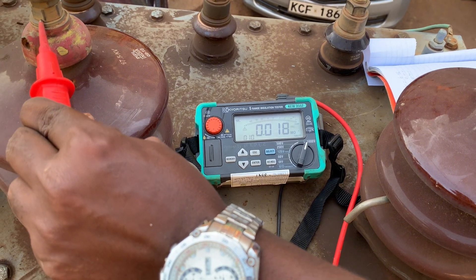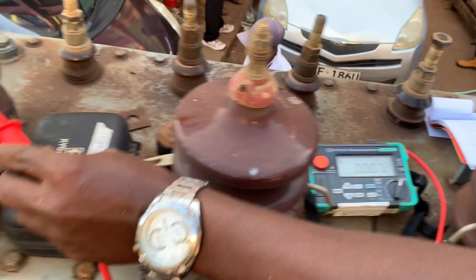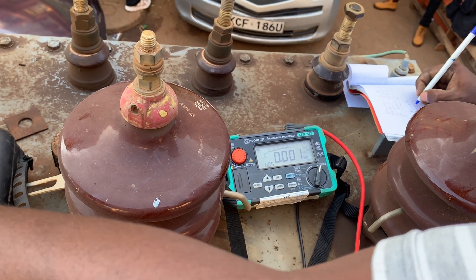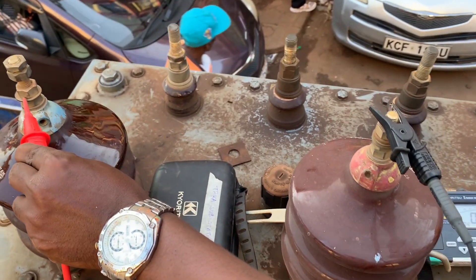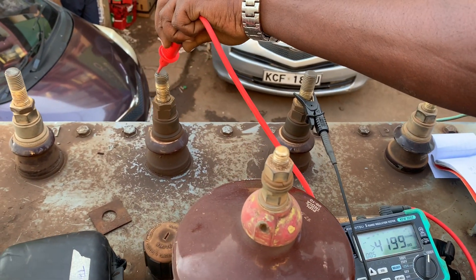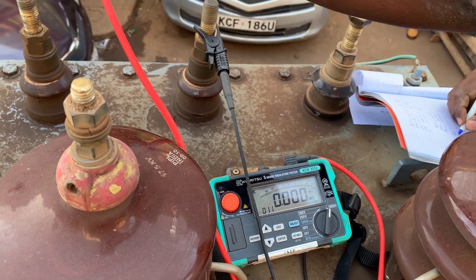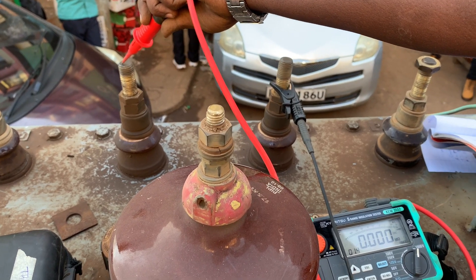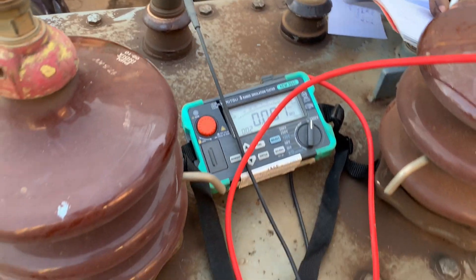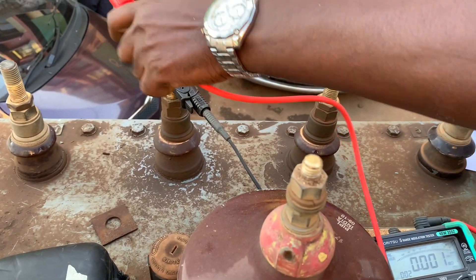That 0.022 reading is correct given that this transformer is a star-delta type. It means the windings inside should give those readings — in other terms, it should give a short circuit between the HT phases. When we go to the LV or low voltage terminations between the phases, we get a short circuit as well, meaning the windings on the secondary are okay, because it has to be like that. That is according to my engineer who was guiding me.